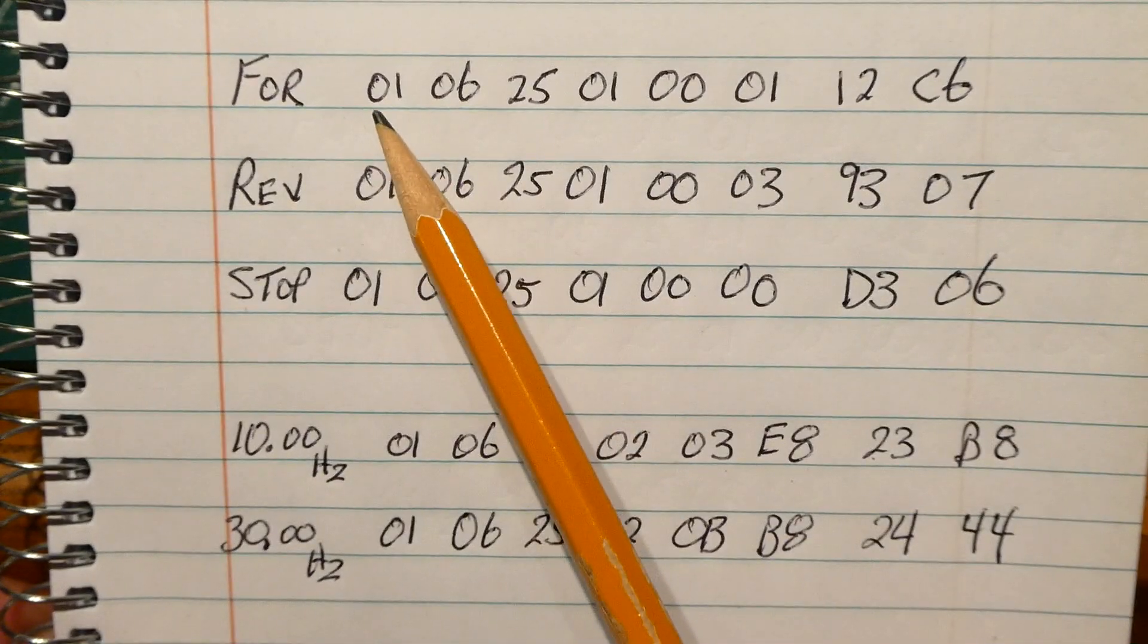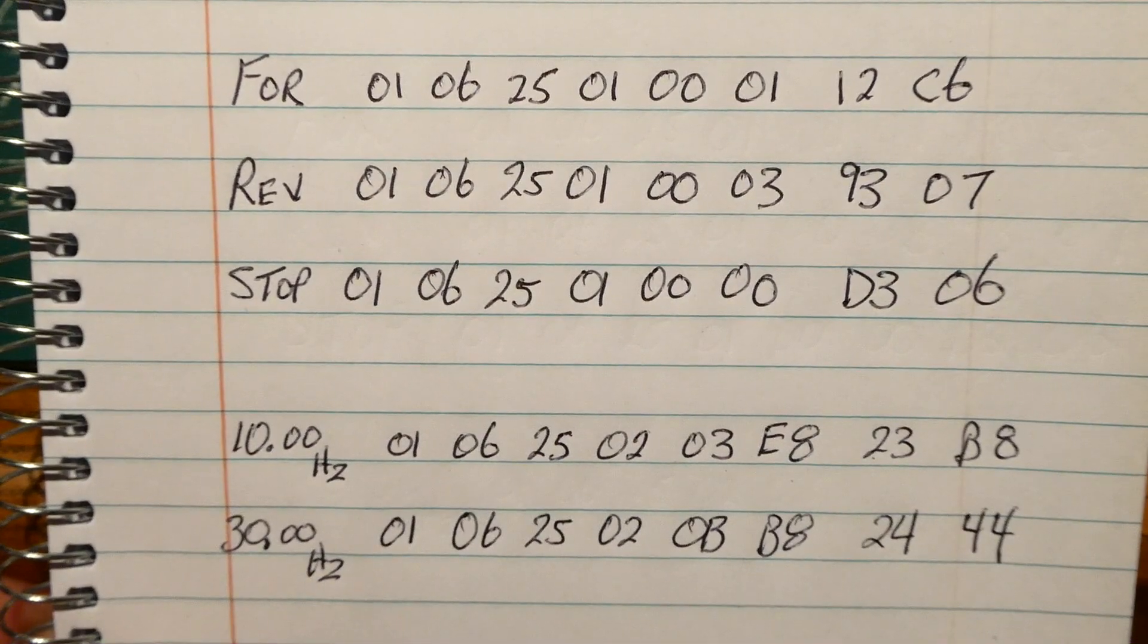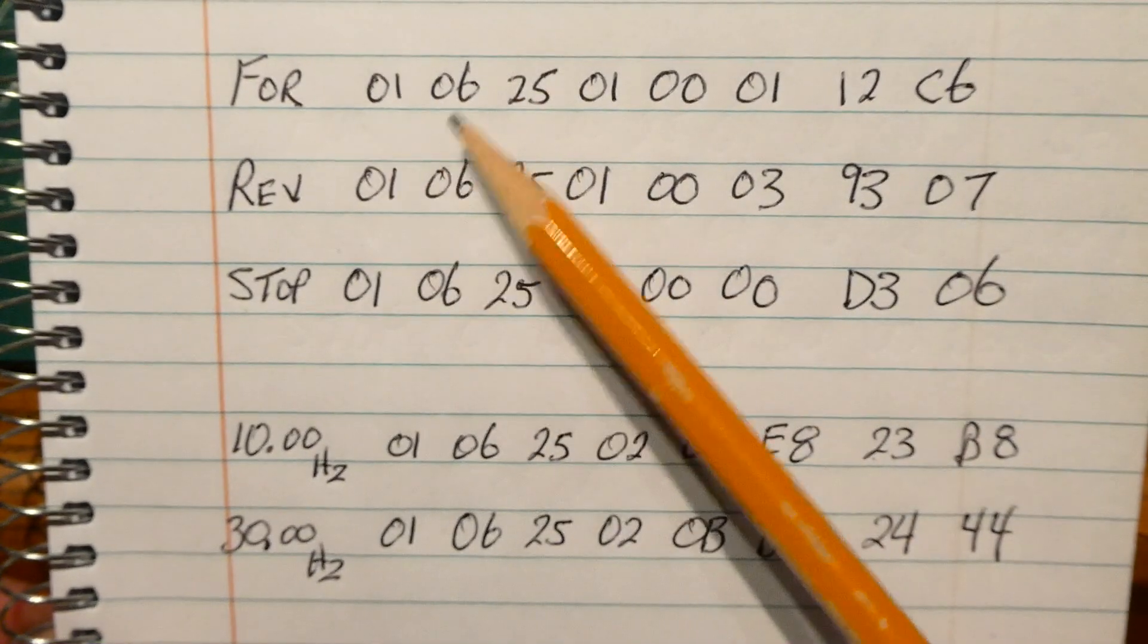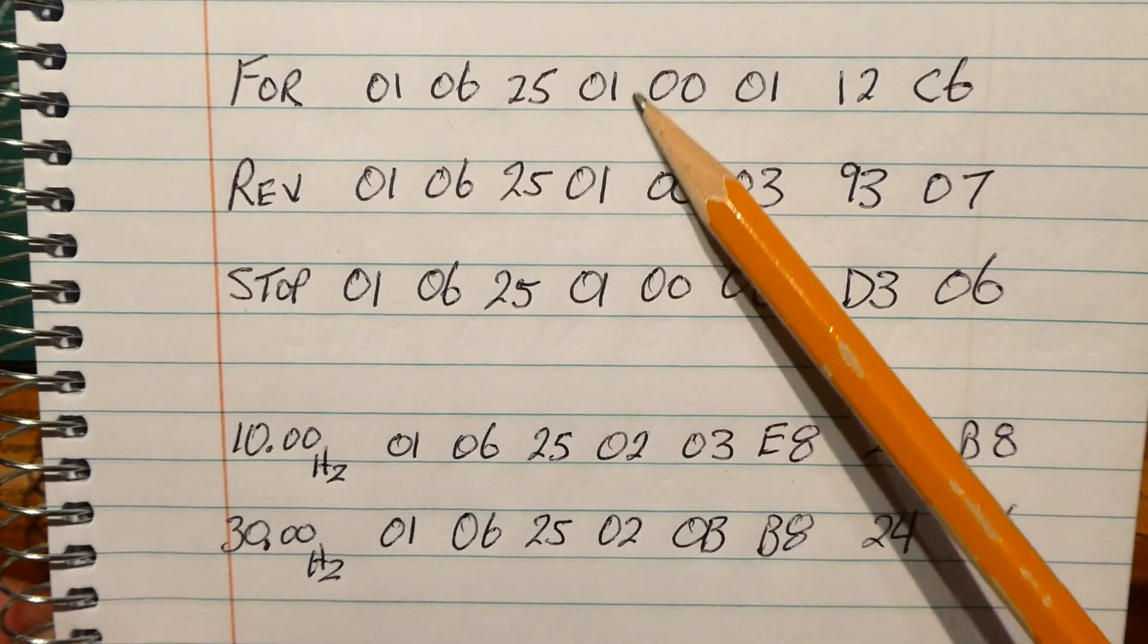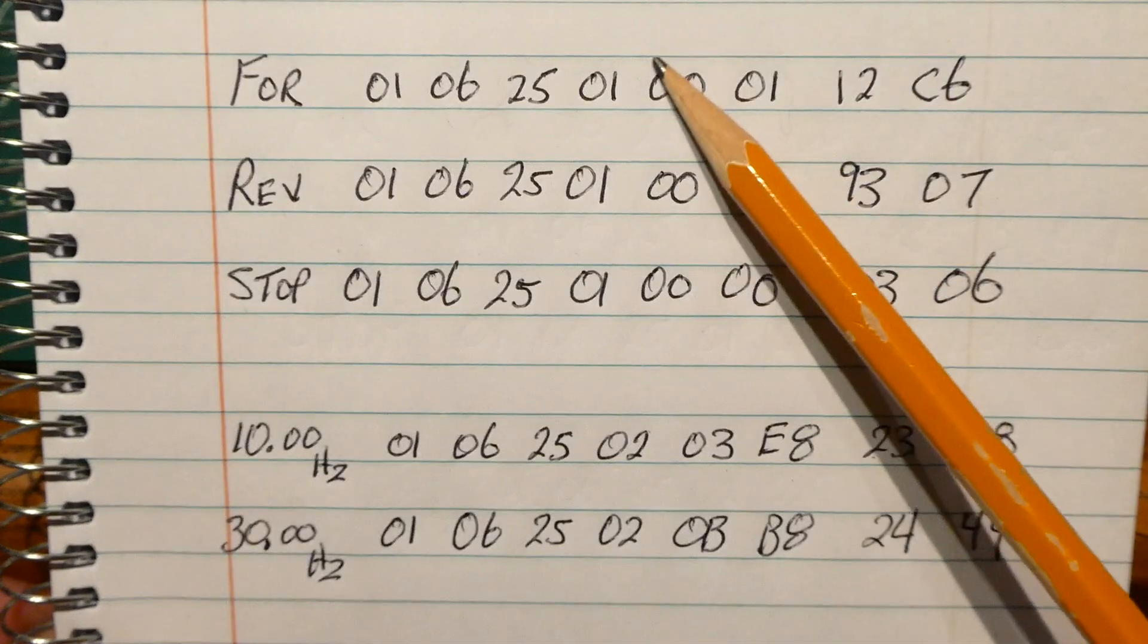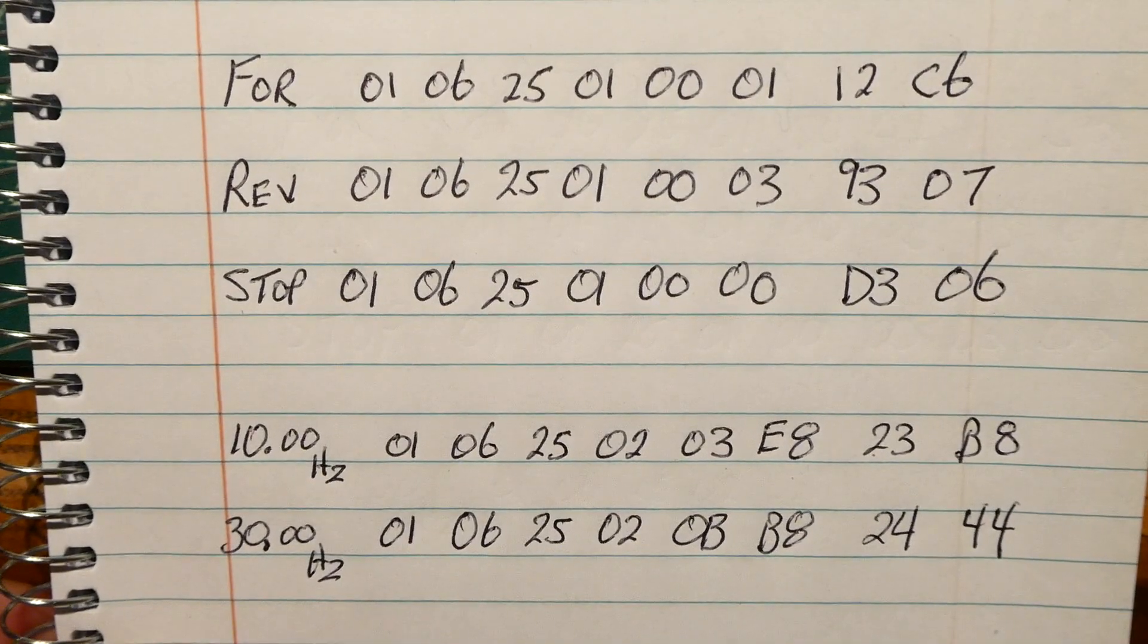So for my forward command, the first byte is the address byte. So every variable frequency drive has its own address, because RS-485 is multi-drop, we could put multiple variable frequency drives on the same pair. So the first byte is address, the second byte means we're doing a write to a register, and these two bytes here, 2501 is the register address, and this is the data that we're writing into that register. And the last two bytes is a 16-bit CRC checksum.